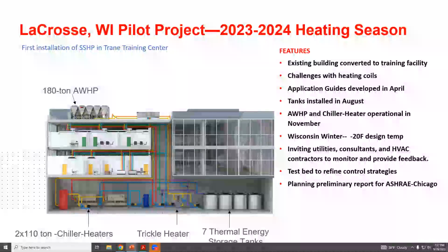The trickle heater comes in if we get into a situation where we don't melt all the ice, or ambients are really cold and we don't have the ability to use our air source product to melt ice. We have backup via an electric resistance system to melt that ice. The entire driver here is to have enough water within our ice tanks to pull from throughout the day.